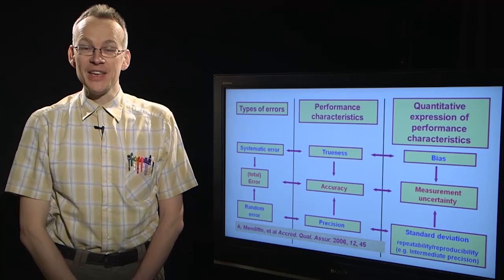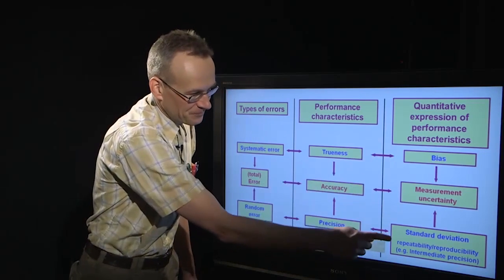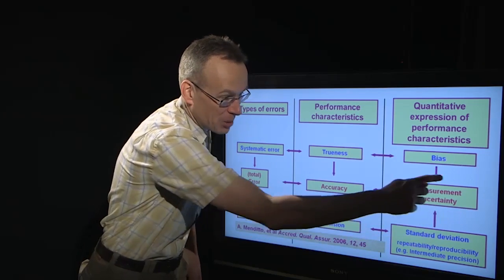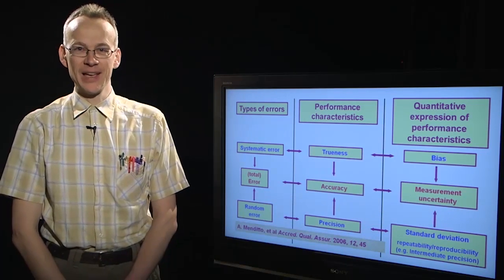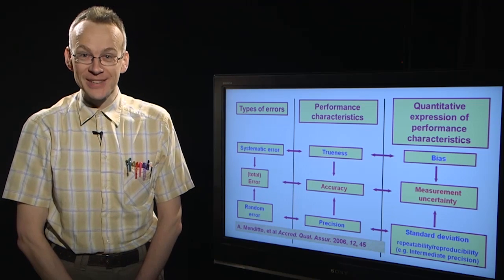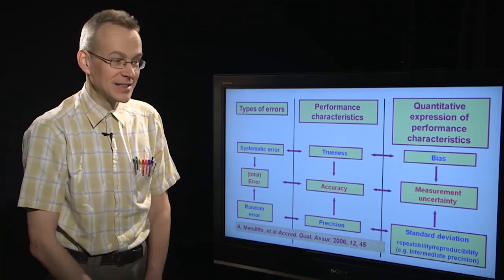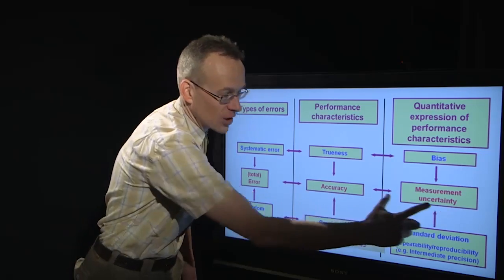If precision by standard deviation and trueness by bias have been estimated in a reasonable way, and if they are cleverly combined in a suitable way, it is possible to estimate the measurement uncertainty. Measurement uncertainty can be called the quantitative estimate of accuracy.